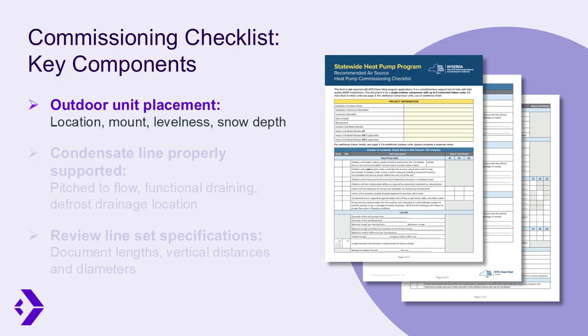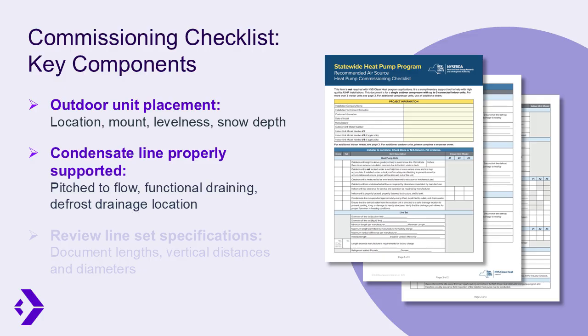Start with the outdoor unit's placement. Verify that it's not directly below the roof drip line, it's on a stand or a wall mount to get it above the region's annual snow depth, and that the unit is level and secure. Double check that it meets the manufacturer's clearance requirements and has an unobstructed airflow.